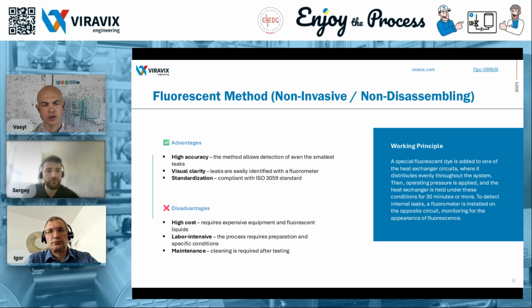Serhi, could you please tell me how difficult it is to remove the dye after this type of test? No, it's not difficult at all. A standard CIP cycle handles this task very well. But a CIP cycle is required after any type of test anyway, right? So basically, this factor doesn't really affect whether it's considered an advantage or a disadvantage. Yes? The only thing is, if there are external leaks, and they're large enough, such leaks will be visible on the outside of the heat exchanger. Leakage? Yes, just minor leakages. So they simply need to be removed, rinsed off with water, and that's it.